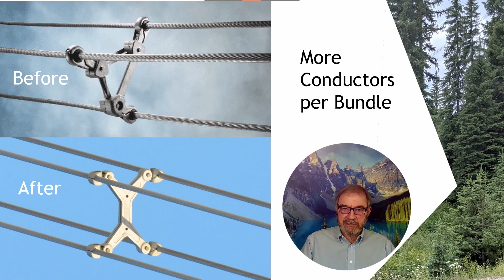Your picture is like the existing bundle of three. The after bundle of four uses the smooth new conductors to double power capacity without significantly increasing weight. Note the Colstrip transmission system portion already has bundles of four. We just have to increase the conductor cross-section and replace the insulators.